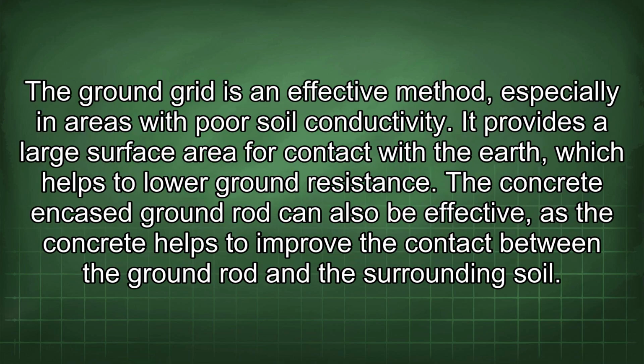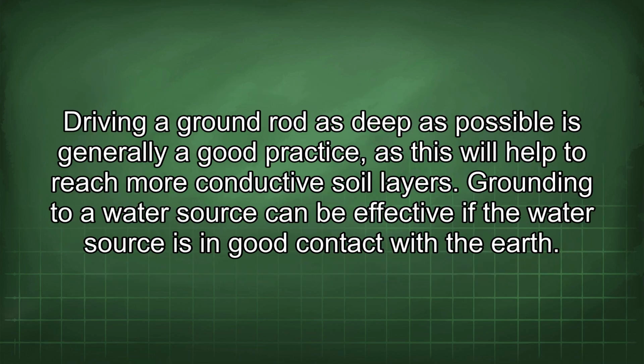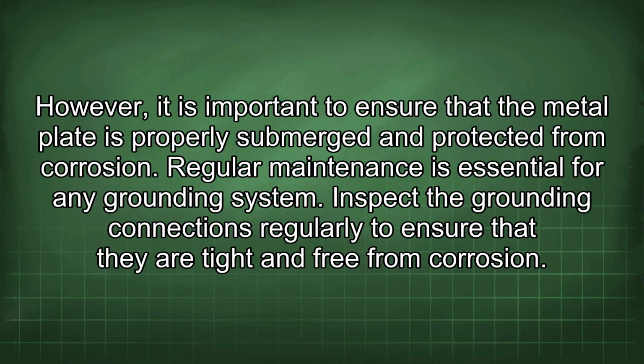The ground grid is an effective method, especially in areas with poor soil conductivity. It provides a large surface area for contact with the earth, which helps to lower ground resistance. The concrete encased ground rod can also be effective, as the concrete helps to improve the contact between the ground rod and the surrounding soil. Driving a ground rod as deep as possible is generally a good practice, as this will help to reach more conductive soil layers. Grounding to a water source can be effective if the water source is in good contact with the earth. However, it is important to ensure that the metal plate is properly submerged and protected from corrosion.